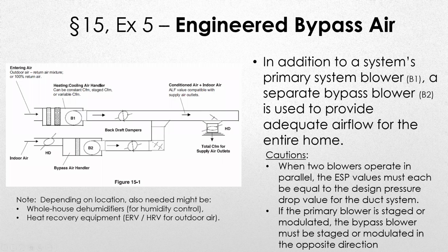The advantage to this is you would only need 2 blowers, where in the mixing box system, maybe you could get by with 2 blowers, but if you were to take off and use smaller mixing boxes, then you might have to have 5 or 6 mixing boxes along with the air handler. With this one, you would just have the 2 blowers. And then, of course, you could need additional dehumidification or heat recovery equipment.